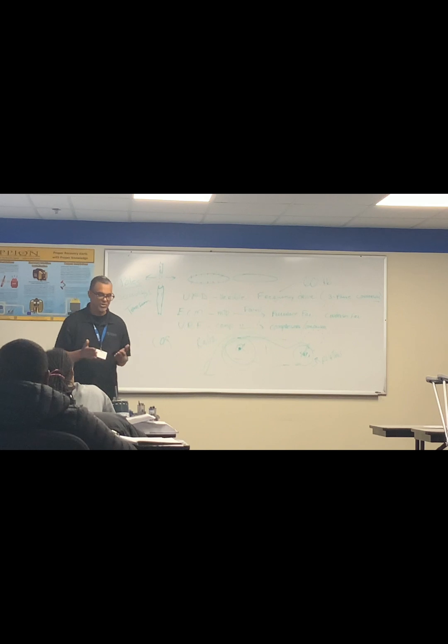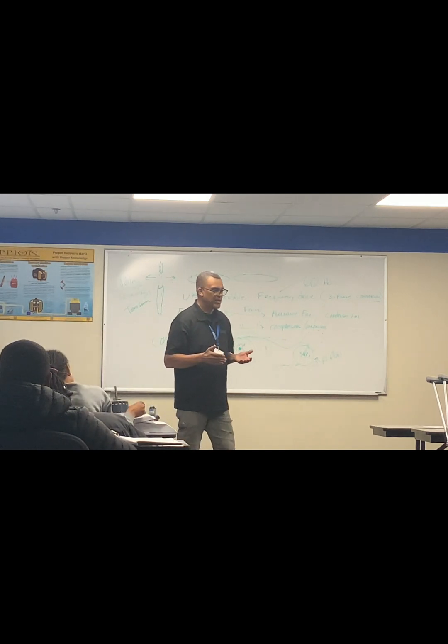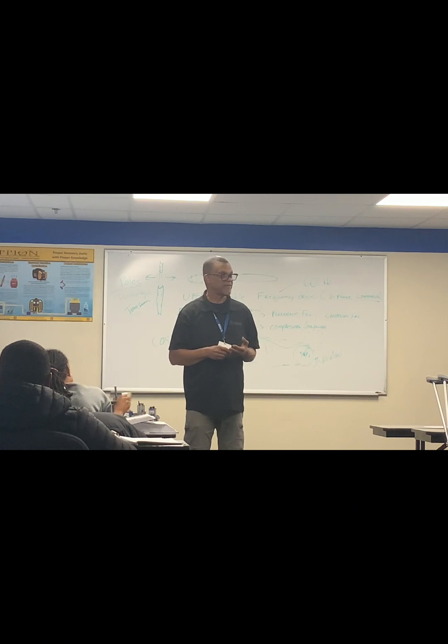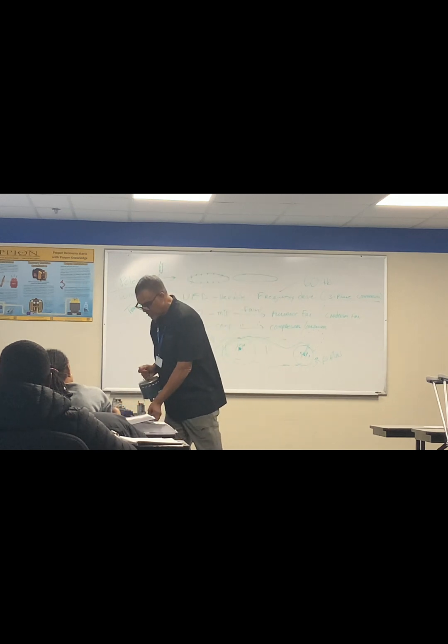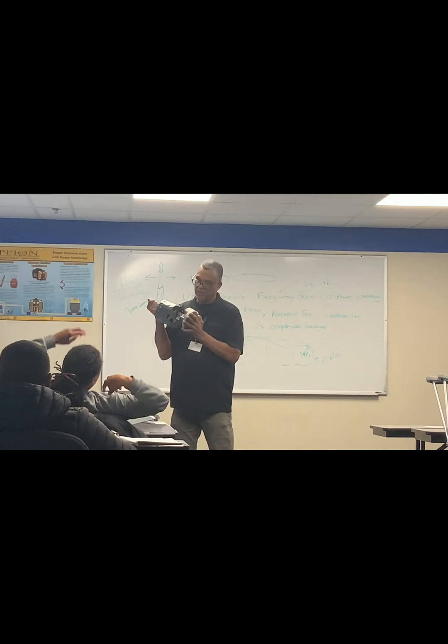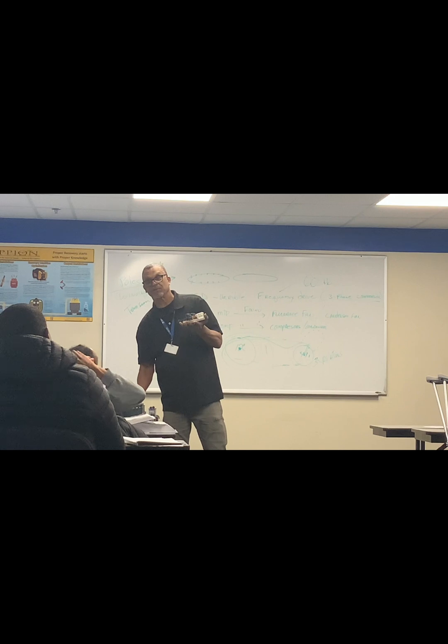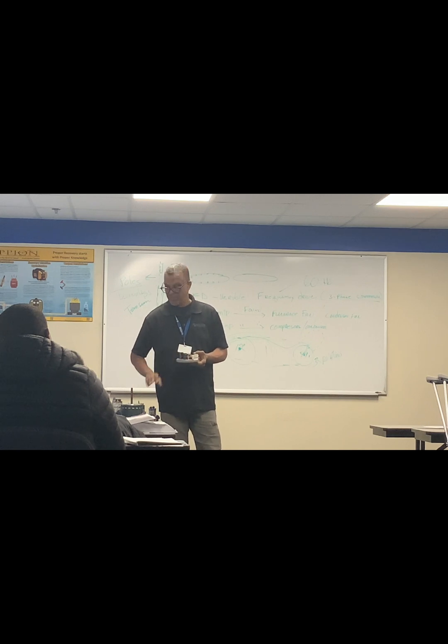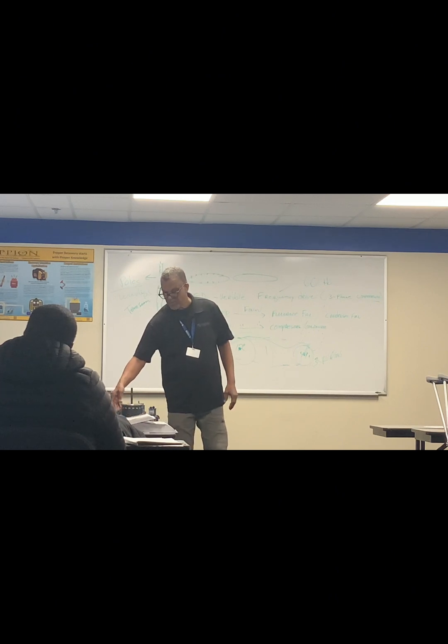Variables are on almost every piece of equipment now. They work a little different in commercial, but in commercial and residential they have the same effect. You'll still see PSC motors around for a long time because they're cheap. These motors might be $1,500. But I noticed the one he showed, because they were so expensive at first, the next group that came out lets you take the bottom off and replace the module. So the module might be $400 and the motor's good. When they first came out, the module and the motor were one piece. You had to buy the whole thing, even when nothing was wrong with the motor, it was the module. They have made upgrades and changes on those pieces of equipment, and it'd probably be a little better to see how they actually work.